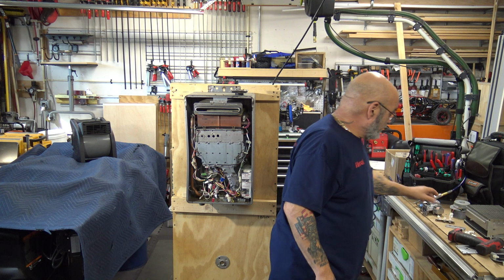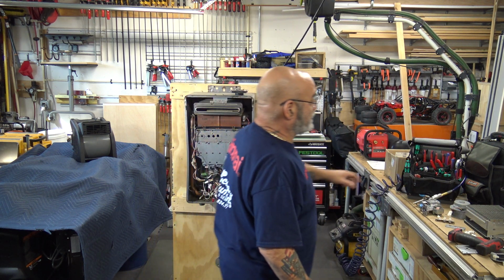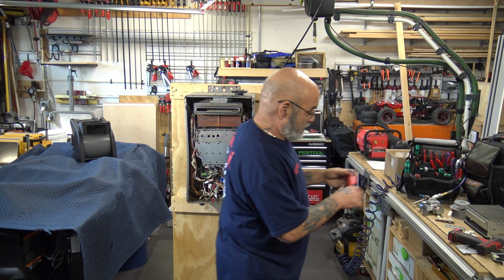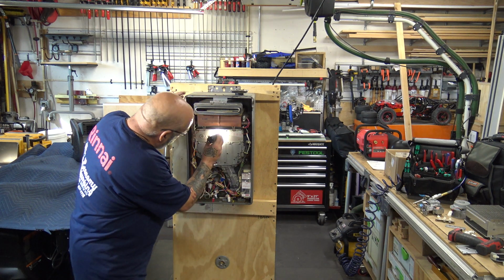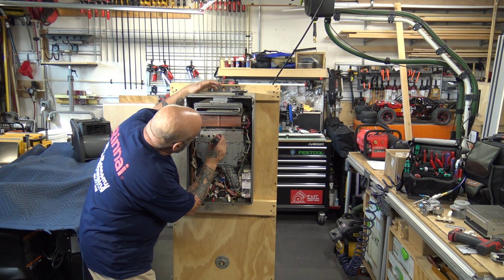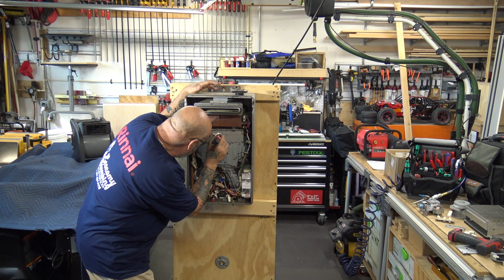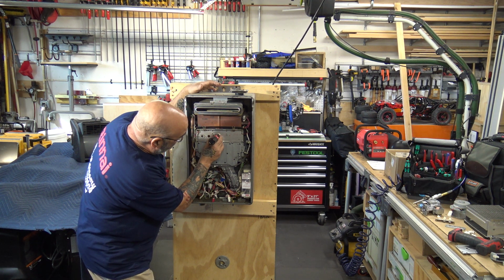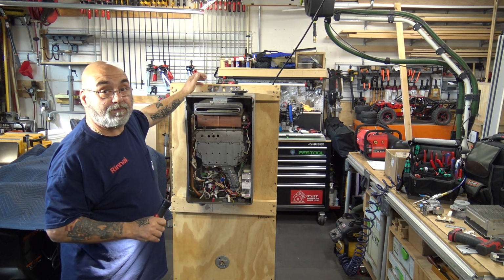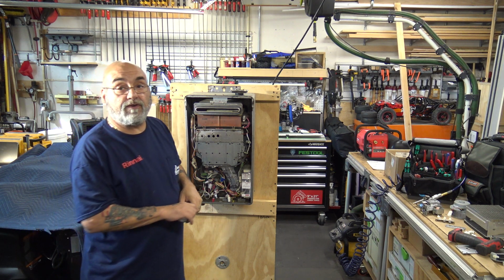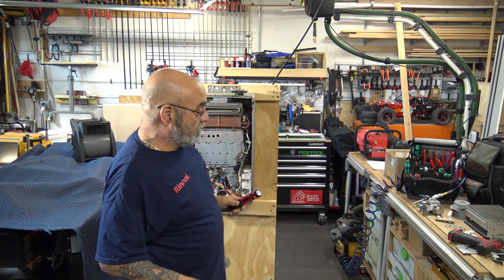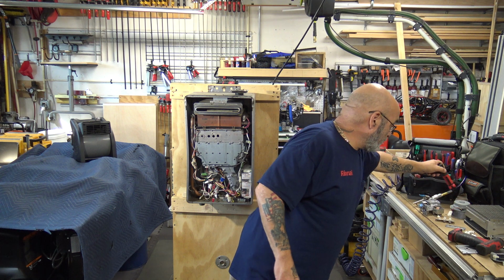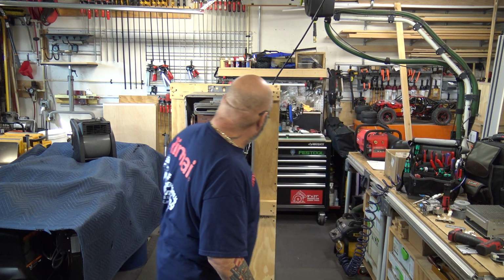So we inspect that, then we're going to take a flashlight and look inside this burner. Just put your light into one of the holes, look in there, and you're going to see that this burner is filled with debris. So now we've got to remove the orifice cover and that top burner plate.